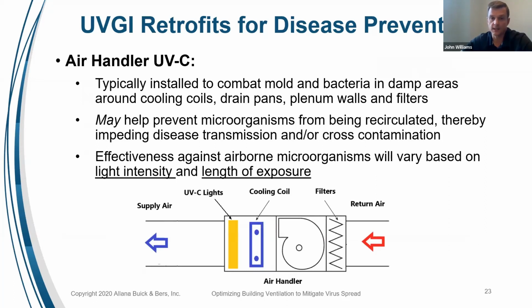Typically when we find UVC lights installed in an air handler, they're installed for the purpose of treating the bacteria on the coil. That cooling coil is condensating and sweating, so we get a lot of bacteria and mold growing back there. So typically the UVC light in there is treating that area and trying to cut down the amount of mold and bacteria. It's not really designed to actually treat the air flowing through the unit. It could potentially have an effect on the airborne microorganisms, but that's really going to vary with the light intensity and the length of exposure.